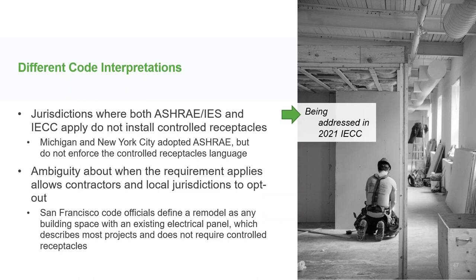As Harold mentioned, the code requiring controlled receptacles is not the only building code out there — it's implemented unevenly across the country. For example, the current IECC code does not require controlled receptacles, and within ASHRAE it only requires them in new construction. So when multiple building codes apply and people can choose which interpretation to apply, they opt for the version that doesn't require controlled receptacles. By expanding requirements and increasing consistency across different applications, more of these projects would get implemented.